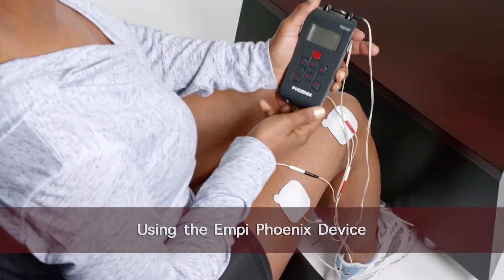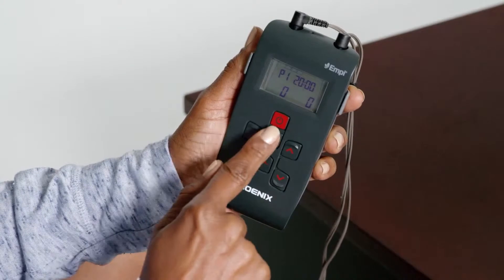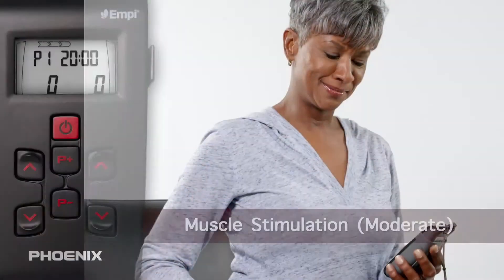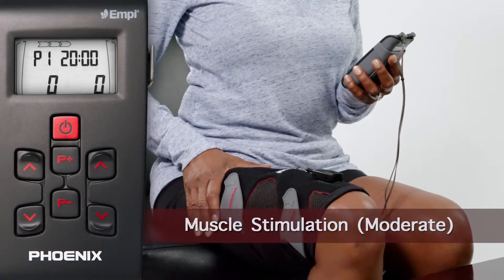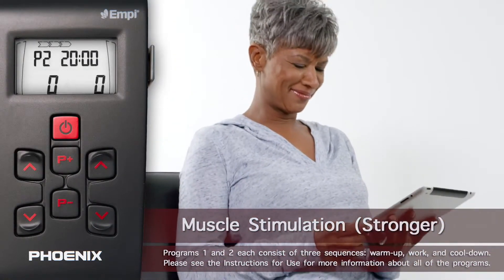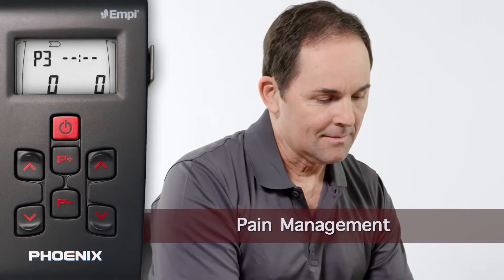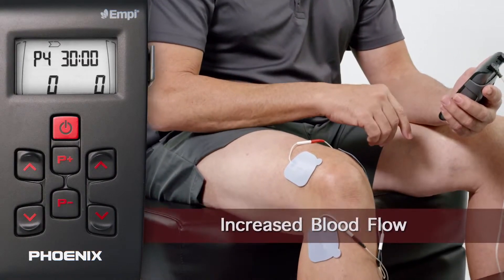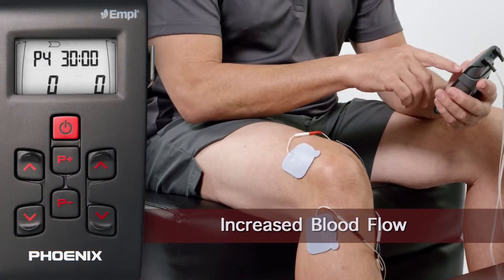Once the device is connected, turn it on by pressing the power button in the upper middle of the device. There are four programs on the Empi Phoenix device. Navigate the device to the program prescribed to you by your healthcare provider. Program 1, or P1, is a neuromuscular electrical stimulation program designed to generate a stronger muscle contraction. Program 3, or P3, is a transcutaneous electrical stimulation program intended to help manage localized pain. Program 4, or P4, is a pulsed direct current program designed to help increase local blood circulation.